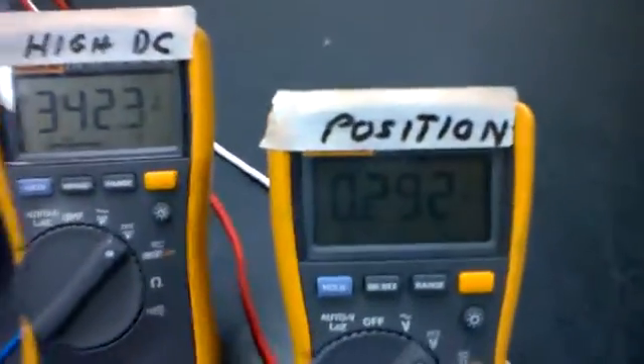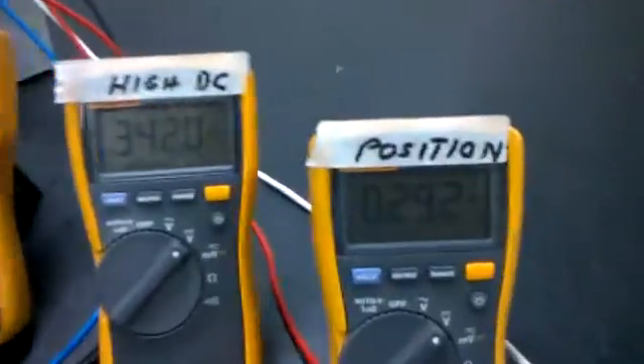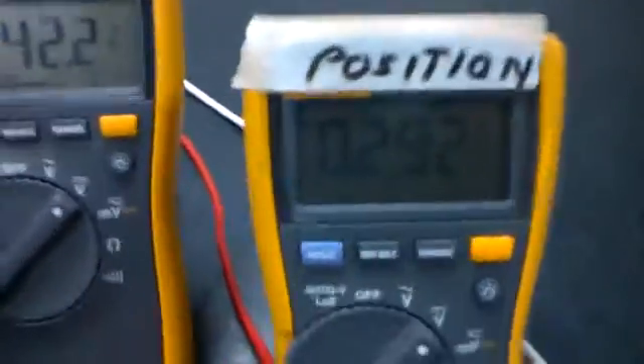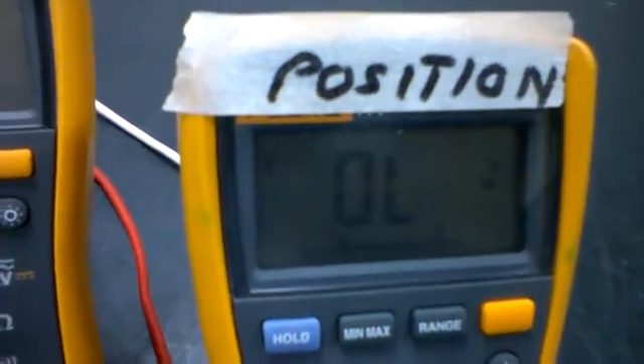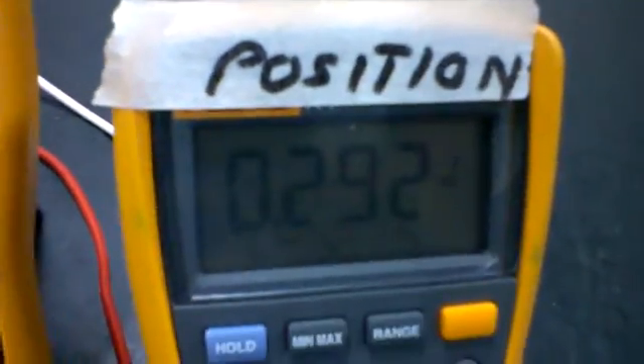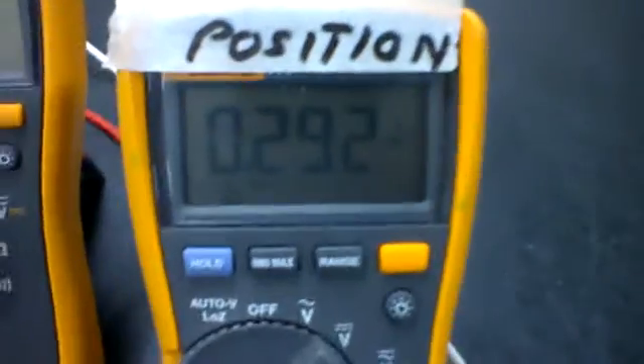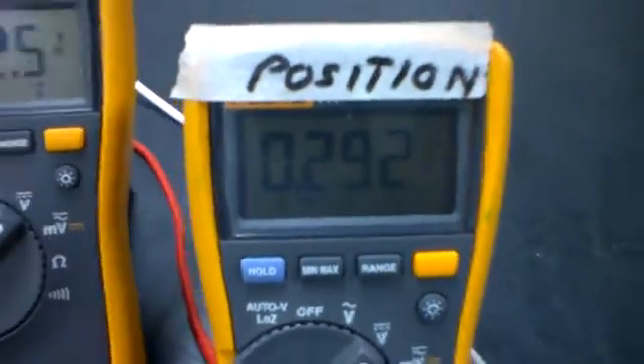When it's actually running, this will be going so fast that it'll almost become one singular voltage. But this is the test that you would do yourself to prove that the position signal is working in the motor. And again, that's not going to work unless we've got our control voltage coming into the unit itself.